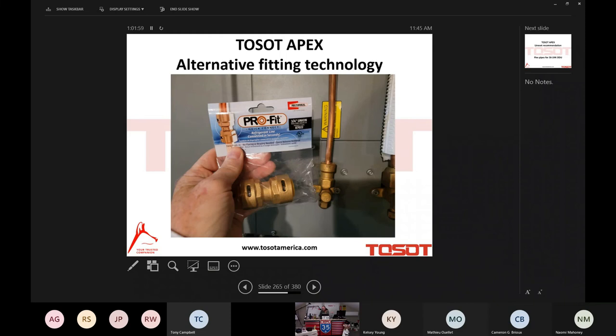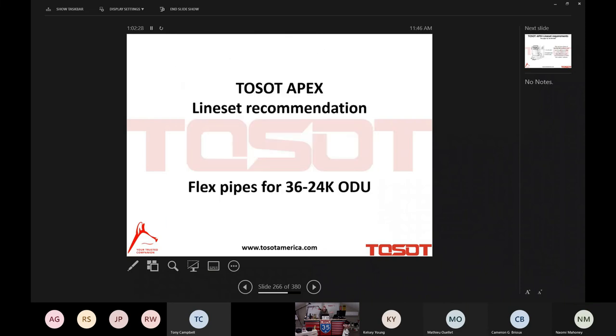And people, here's the bottom line. Works beautifully. Held 500 PSI of nitrogen. Held a vacuum down to 500 microns. And the bottom line is holding the refrigerant, and the system runs beautifully. So, you know, this is technology, and I accept it, and I love it, and I've become a big fan of it, to be honest with you. All righty, we move along.